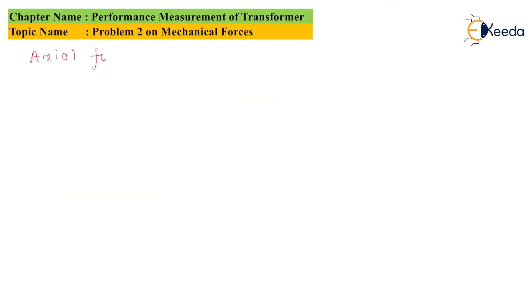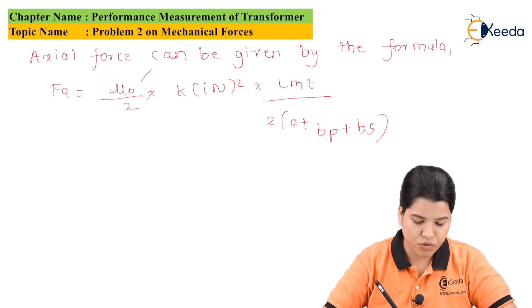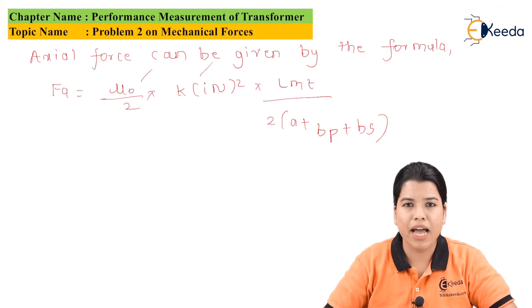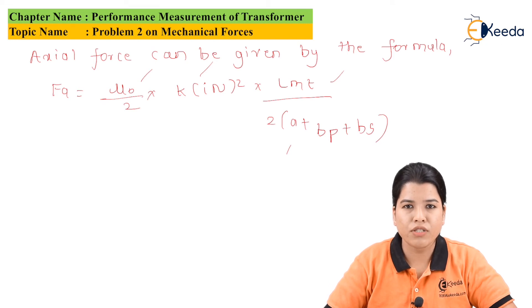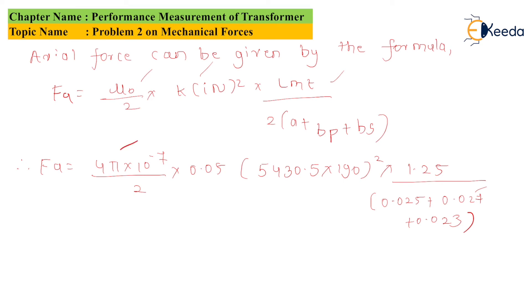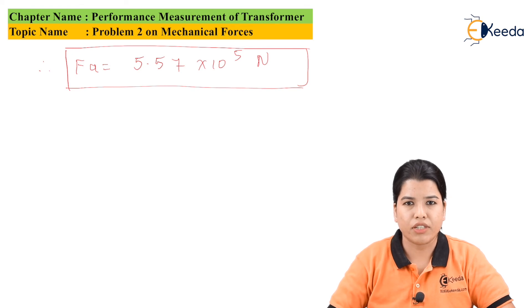Now let us find the axial force for the second condition. The axial force Fa is given by: Fa = (μ₀ / 2) × K × In² × LMT / (2 × (a + Bp + Bs)). Substituting the values: Fa = (4π × 10⁻⁷ / 2) × 0.05 × (5430.5 × 190)² × 1.25 / (0.025 + 0.027 + 0.023). After solving, Fa = 5.57 × 10⁵ Newton.